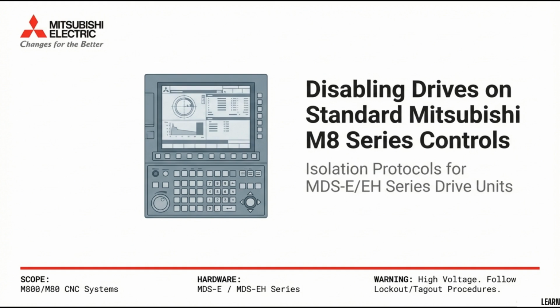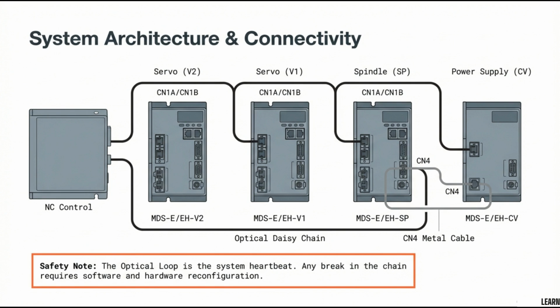This video covers isolation protocols for MDS-E/EH series drive units used in M800/M80 CNC systems. Remember that these procedures involve high voltage and require following proper lockout/tagout procedures. The system architecture connects the NC control to the drive units via an optical daisy chain. A safety note: the optical loop is the system heartbeat, and any break requires both software and hardware reconfiguration.